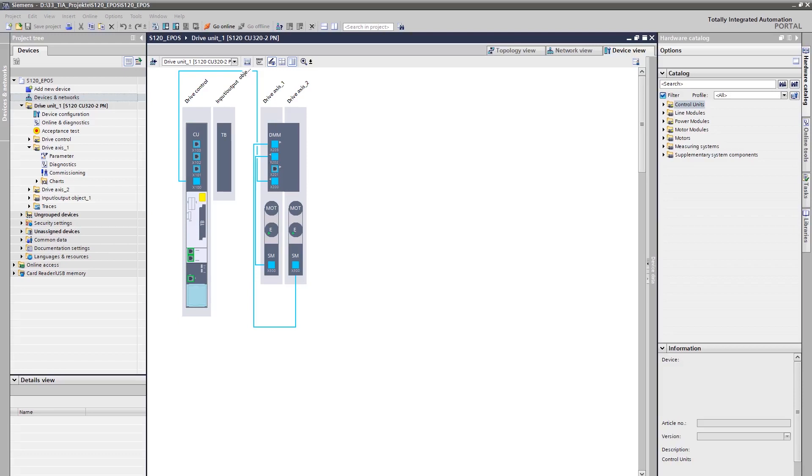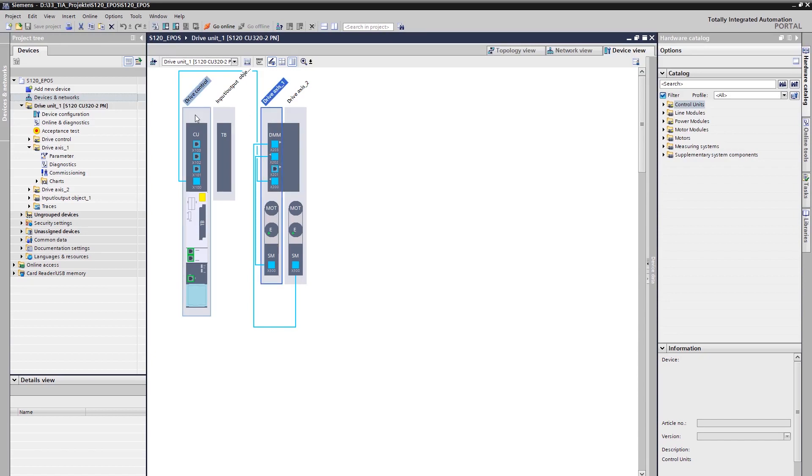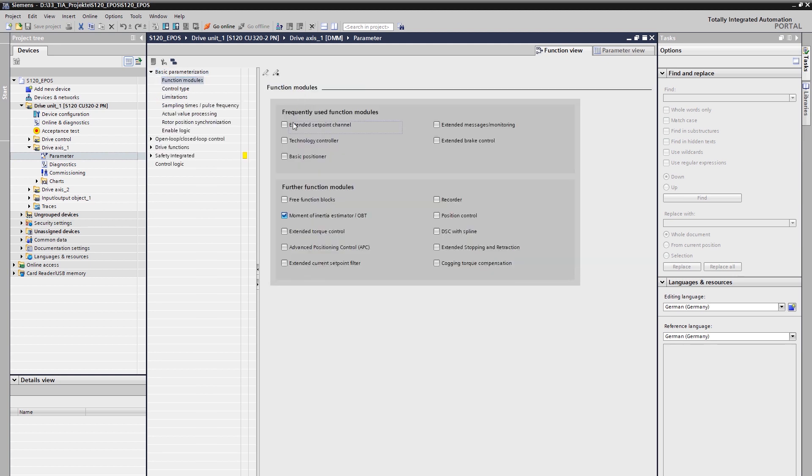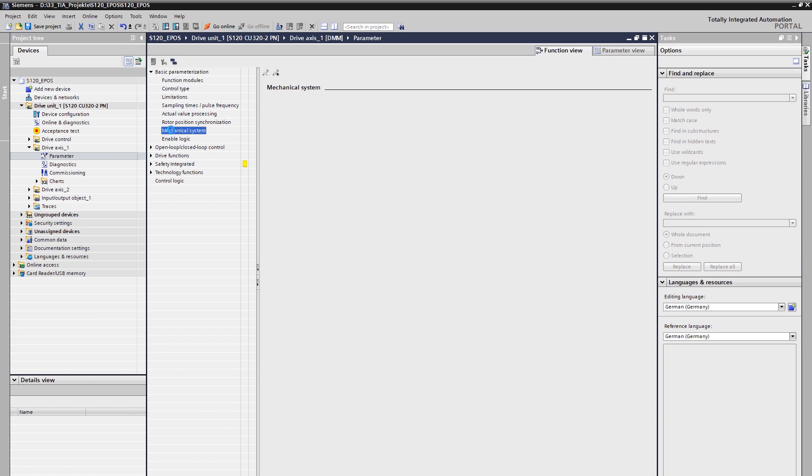Let's start with the configuration in Startdrive. In our project, we find an already commissioned drive unit with two axes configured. For the first axis, we want to activate the positioning functionality. Therefore, we have to activate the function module basic positioner in the function view of the basic parameterization. As you see, the position controller function module is also activated implicitly. Under the basic parameterization node, the entries for mechanics and technology functions are becoming visible.